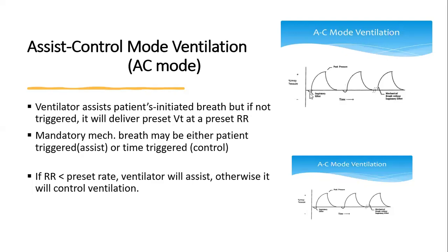All right, so the ventilator detects the attempt of the patient to take a breath and boosts that respiratory pressure. But if the ventilator waits and the patient does not initiate any breath, the ventilator goes ahead and delivers the tidal volume that has been set at the set respiratory rate. So altogether, the ventilator does its job, but it waits for the patient to initiate a breath. And if the patient does not initiate a breath, the ventilator goes ahead to deliver the tidal volume and the respiratory rate that you have set.